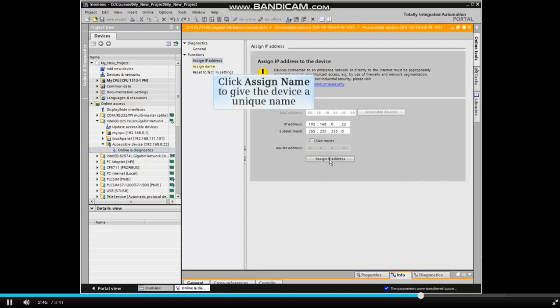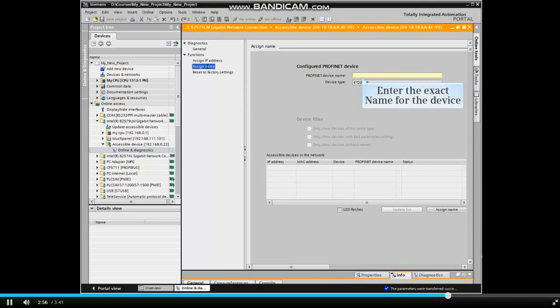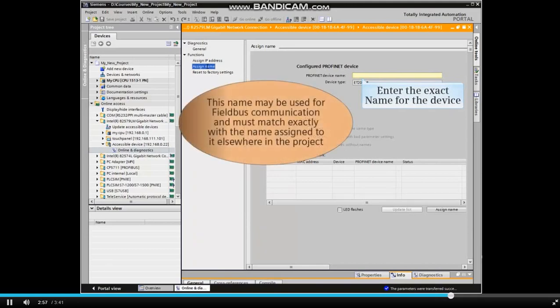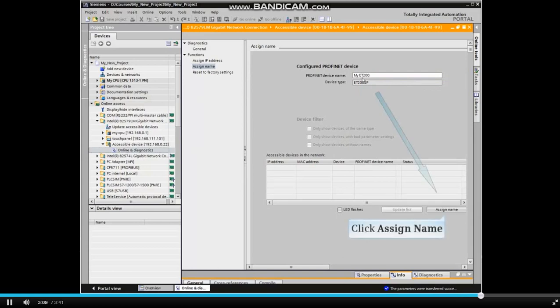Now we will give the device a unique name required for the network application. Click Assign Name from the functions menu. Enter the exact name for the device. This name may be used for field bus communication and must match exactly with the name assigned to it elsewhere in the project. When the name is entered, click the Assign Name button.